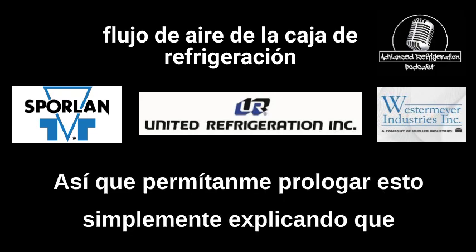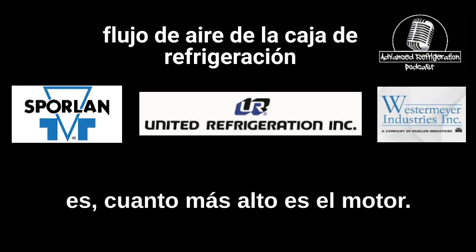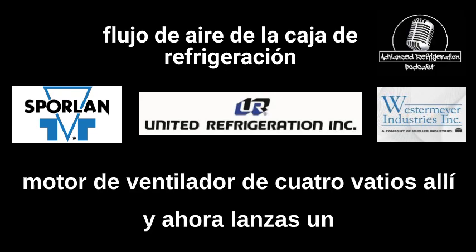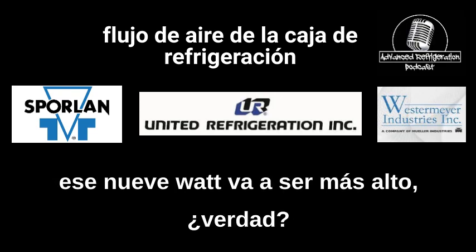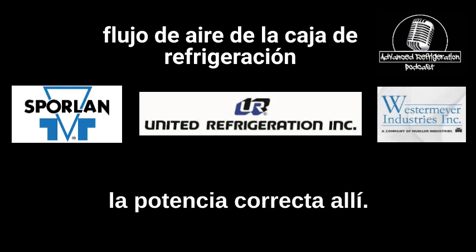So let me preface this by explaining that typically with non-ECM motors, the more wattage it is, the taller the motor is. So if originally you had a Hussmann case that had a 4-watt fan motor in there, and you now throw a 9-watt fan motor in there, basically that 9-watt is going to be taller, right? So make sure you're putting the correct wattage in there.